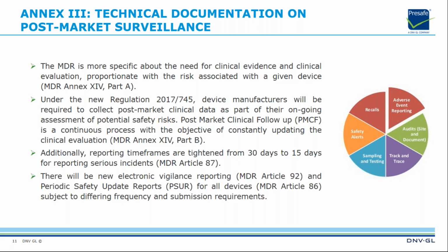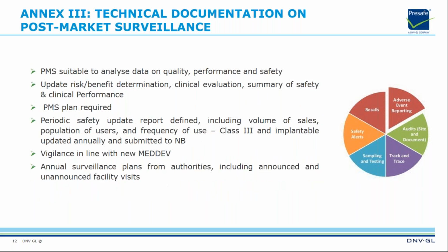Additionally, reporting timeframes are tightened from 30 days to 15 days for reporting serious incidents. There will be new electronic vigilance reporting and a periodic safety update report for all devices, subject to differing frequency and submission requirements.